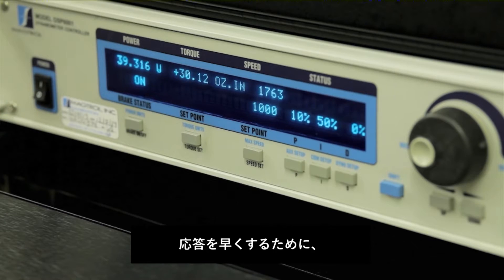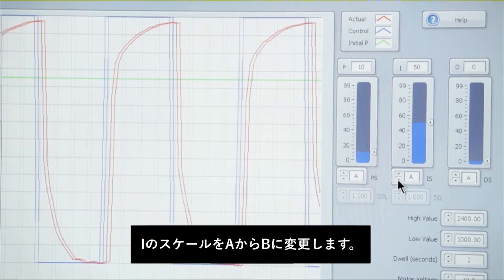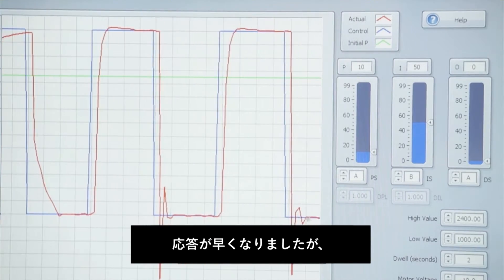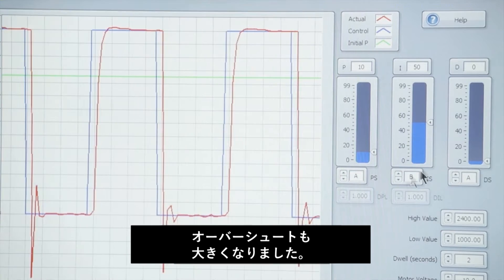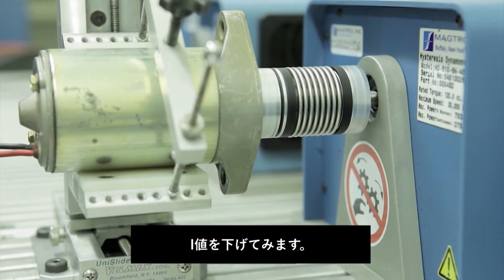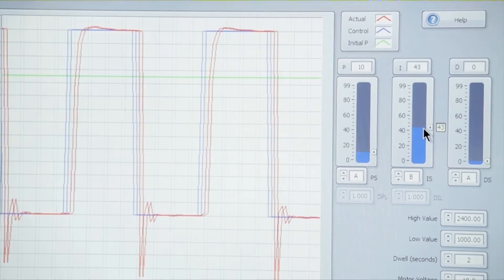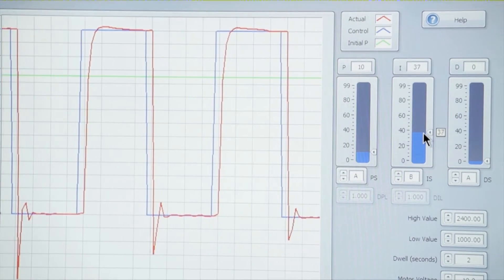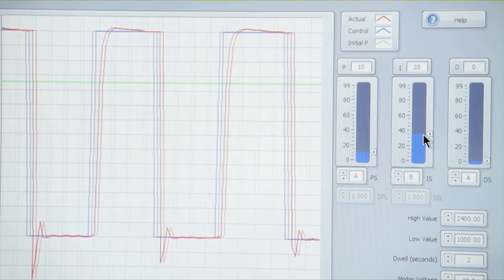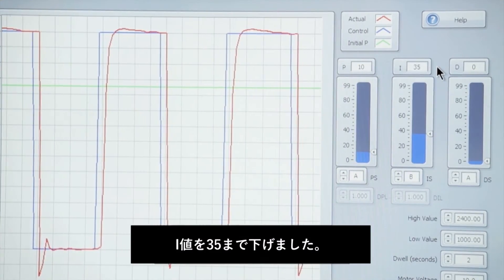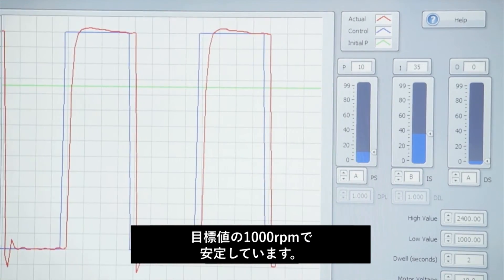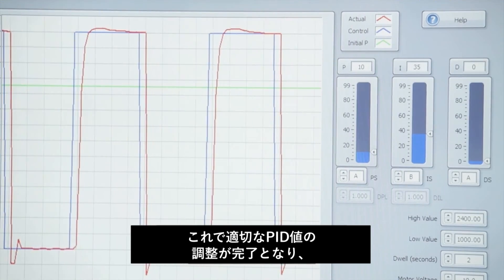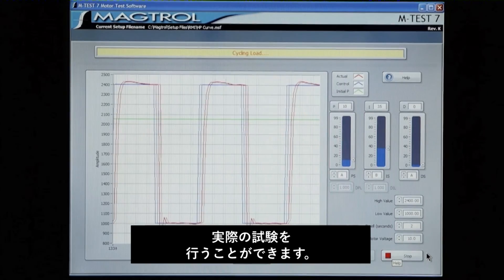In order to speed up that response we'll change our I scale to the next value, B. Now you can see that we are getting to our target much faster, but we have a fairly large amount of overshoot, so we want to bring that overshoot down by adjusting the I term to a lower value. At this point we've decreased our I term to 35 — we have a small amount of overshoot and it settles in nicely at our target speed of 1,000 rpm. Our adjustments are set at proper values to continue on with our motor test.